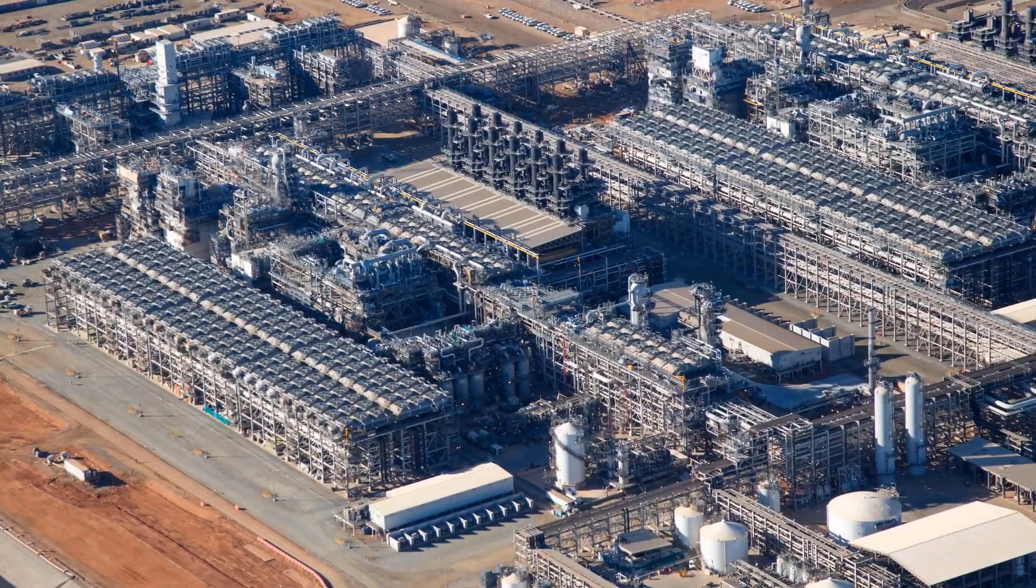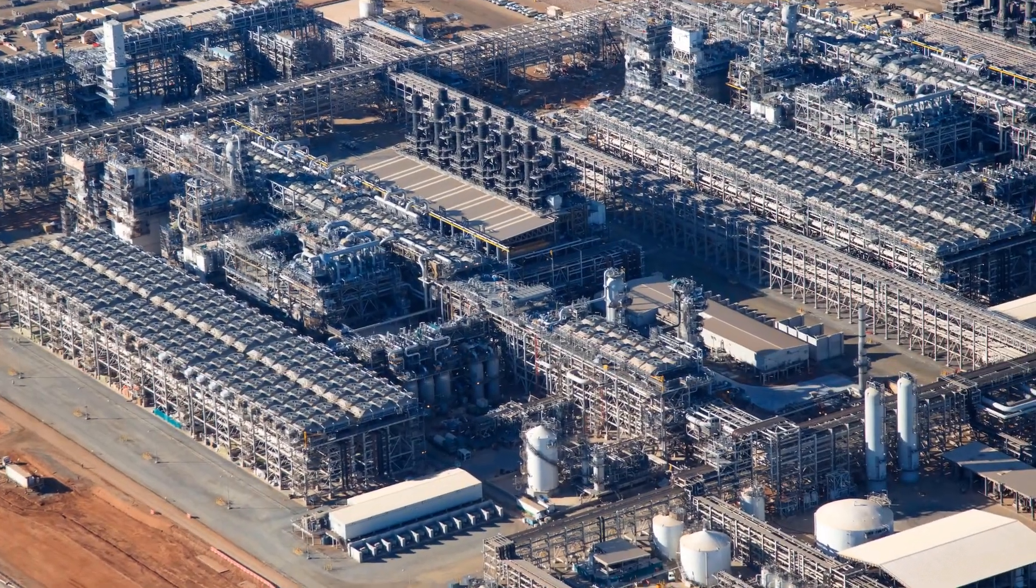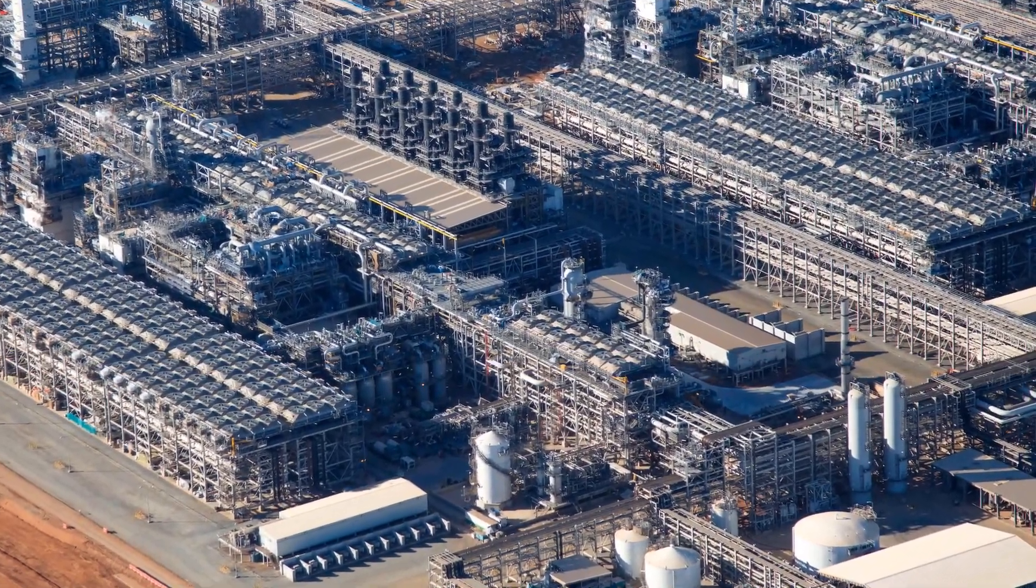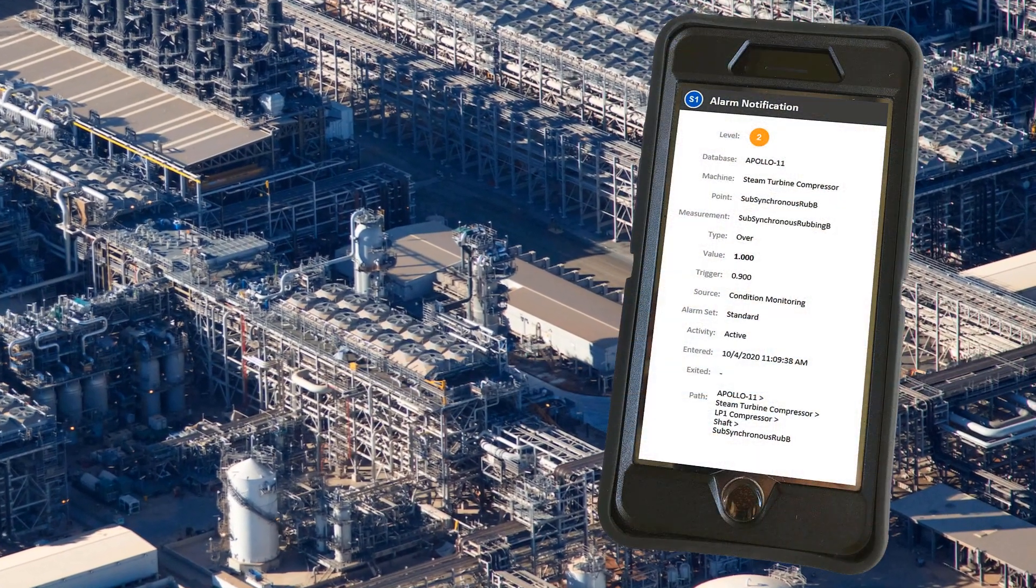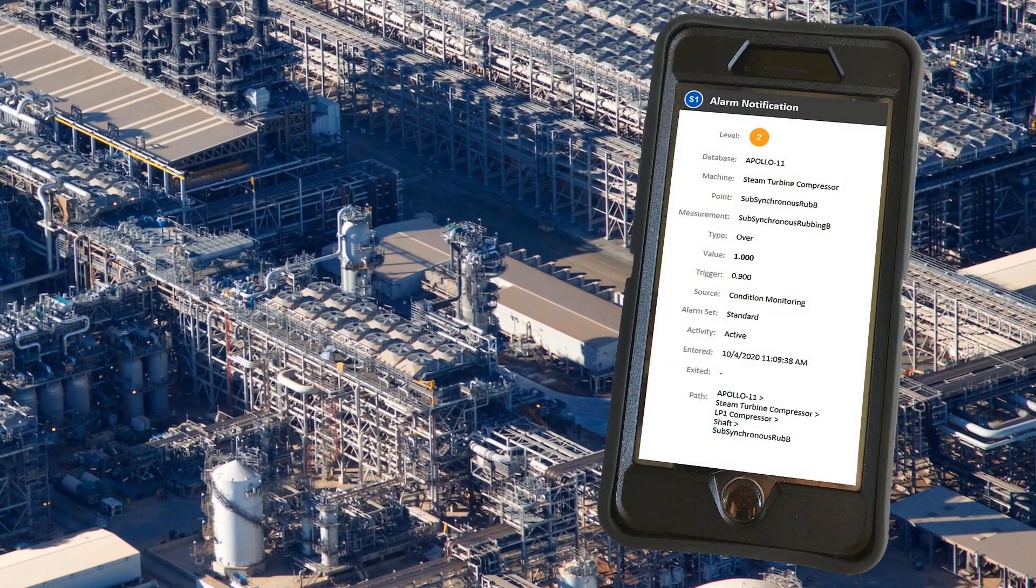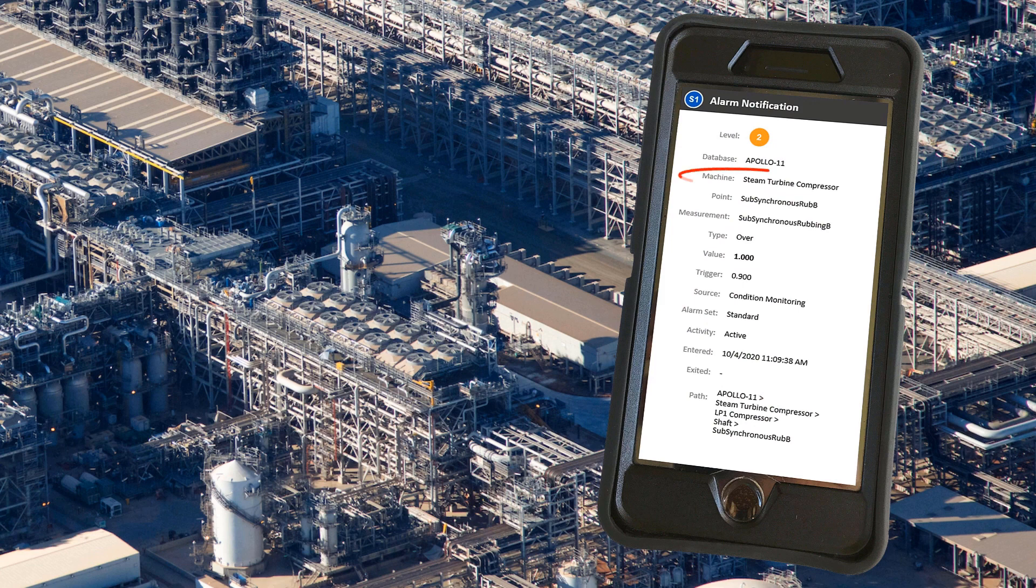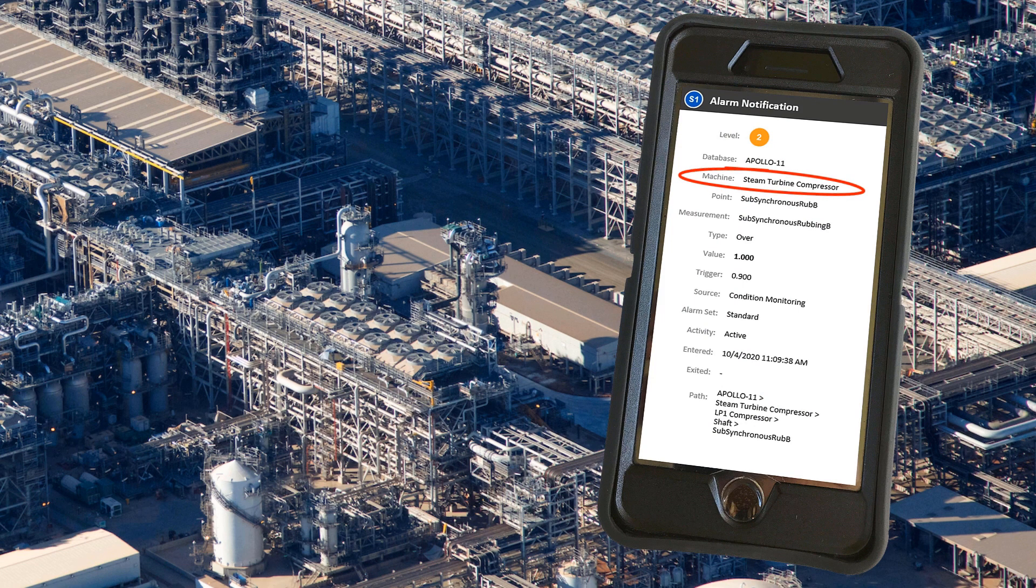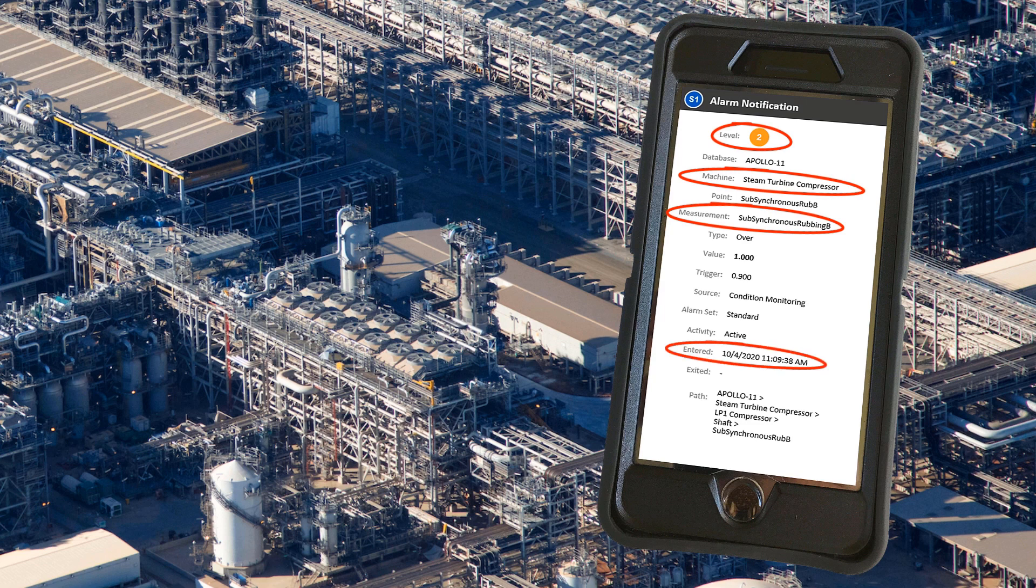Within the production facility, System One has detected and notified targeted staff of a failure mode on a critical compressor. The notification highlights the machine where the problem exists, the severity condition, the failure mode, and date and timestamp of the event.